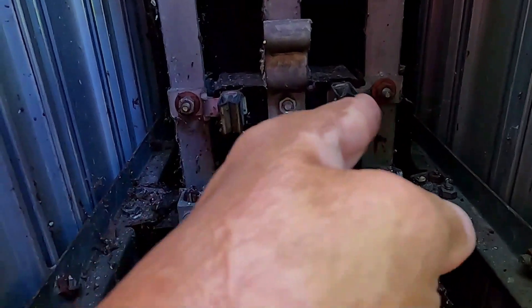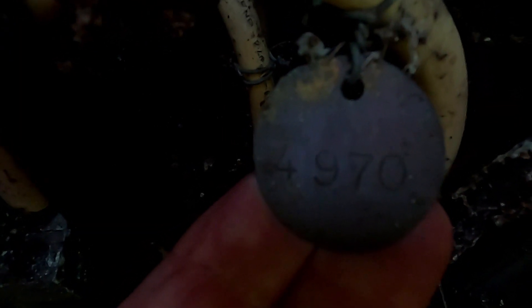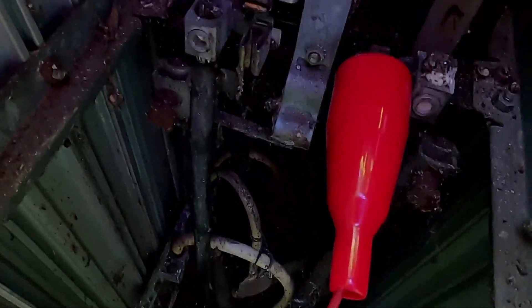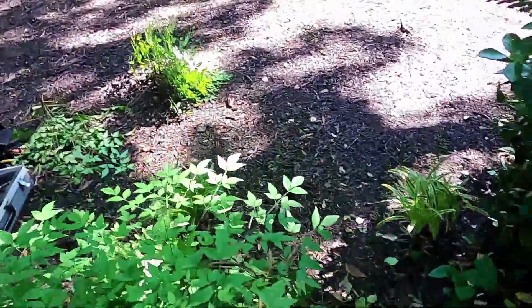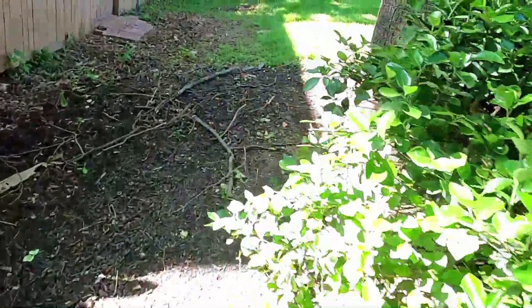The power is coming in on these two here, and you can see how they come up out of the ground. On one of the conductors is our target address 4970. Originally the customer said it was in here, but it really wasn't — at some point they moved the shields and put them back in improperly in the wrong location, and that's what was giving us a delay getting started on this cable trace. So what we do is hook up our tone generator — we're putting a signal on the cable going underground. There's a grounding point here that's the return.